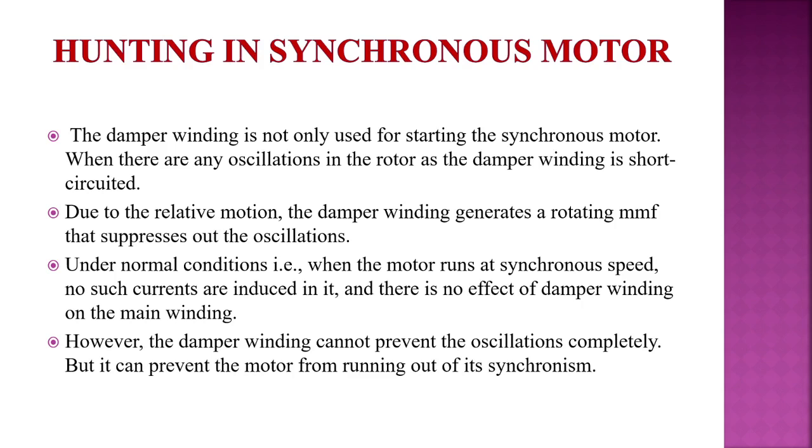So in the first class we have seen that damper winding is used to start the synchronous motor because it requires the starter in the starting. So damper winding is not only used to start the synchronous motor, it will also generate rotating MMF that will suppress the oscillations. So it has two effects here. Under normal conditions, that is when the rotor runs at synchronous speed, no such currents are induced in it, and there is no effect of damper winding on the main winding.